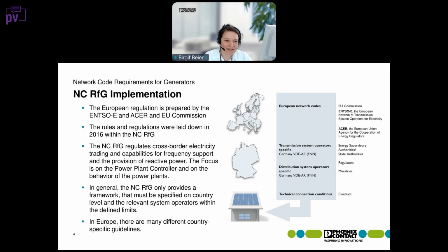The NCRFG regulates cross-border electricity trading and capabilities for frequency support and the provision of reactive power. The focus is on the power plant controller, or the PCU as we call it, and on the behavior of every power plant. On the right-hand side, I wanted to show the different levels: the European level on the top, with all the authorities; in the middle, the member states, for example Germany, with specific regulations for the transmission system operators and the distribution system operators. And then on the level of the power plant, we have the contract with the grid operators and the technical connection conditions of the grid operators. And in Europe, we do have many different country-specific guidelines. So, the next slide.